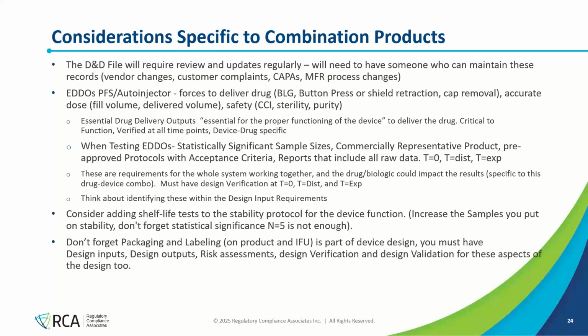So when you're testing your EDDOs for design verification, remember, outputs meet the inputs in design verification. You want to use a statistically significant sample size. This is not an N of 5. You always want to test a statistically significant sample size because design verification requires statistical significance. You want to use commercially representative products. Try not to use hand-built prototype type things. Try to use stuff that went through the fill line, has drug in it, not water-filled devices, things like that. Protocols have to be approved in advance and have to define acceptance criteria in advance, and the reports have to include all the raw data. So, like I said, this is what you would test at T0, T after distribution, and T at expiry.